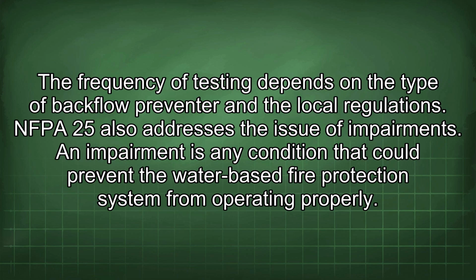NFPA 25 also addresses the issue of impairments. An impairment is any condition that could prevent the water-based fire protection system from operating properly.